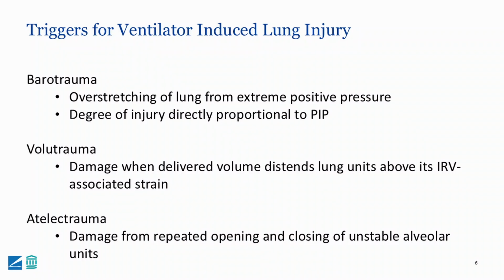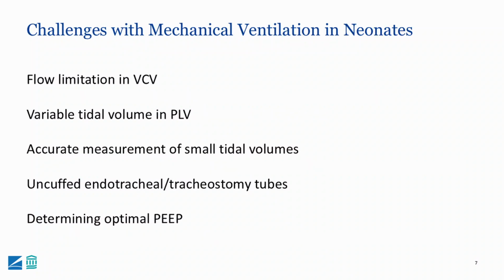There are several challenges when ventilating a neonate, and they're all exacerbated when you think about ventilating an extremely low birth weight neonate. Sometimes we want to control for that tidal volume, and as we think about adult ventilation, we often think about volume control ventilation, but there is flow limitation. The flow in volume control ventilation is set and fixed during inspiration. So if the infant and/or adult has varying flow demands, they will not be met by the ventilator, and that will produce some patient-ventilator asynchrony.